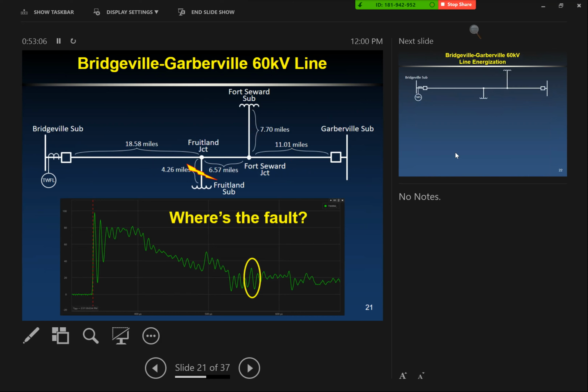So I'll go through this event later, because actually we were able to provide a fault location for this. It's because operators took action—once you energize the line, that gives a different characteristic than the initial fault. And then also when you start sectionalizing the line, you get a cleaner picture. So we'll go through this event and see how that plays out. Just wanted to throw that out there, though.